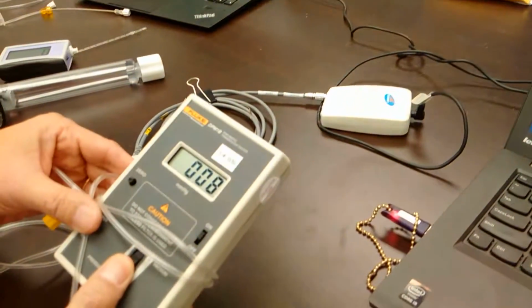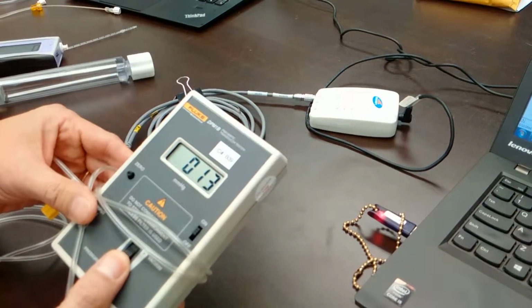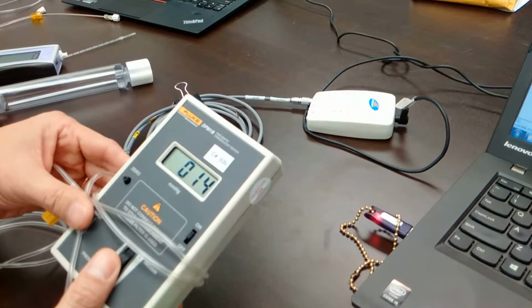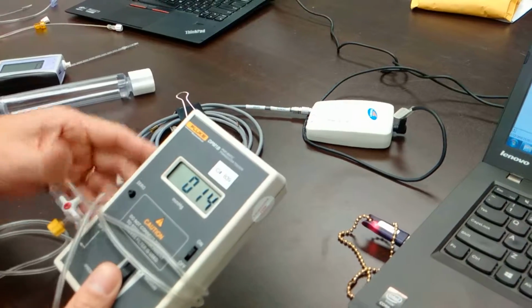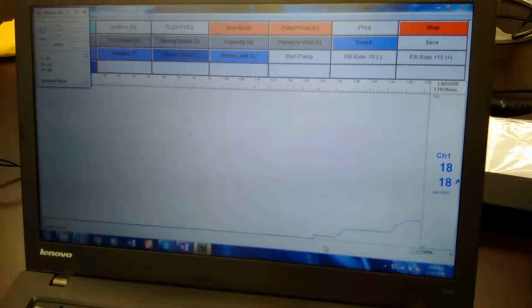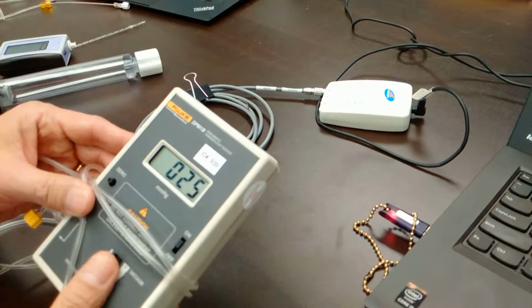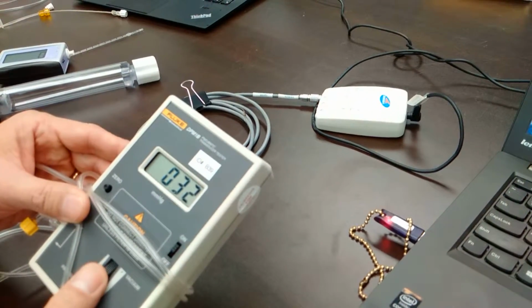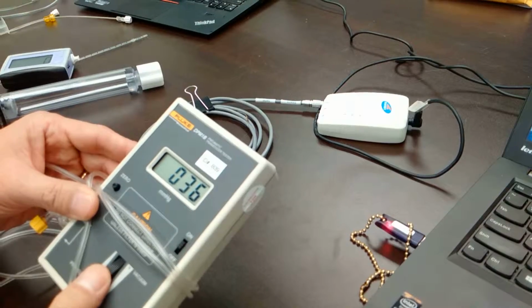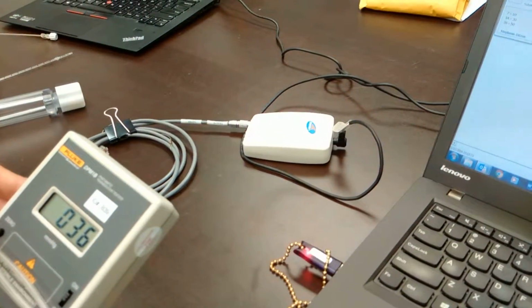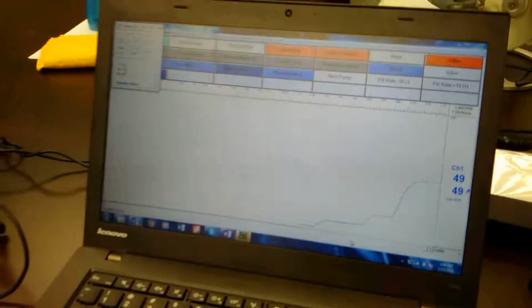If we go to 14, you'll see you get about 18. It's supposed to be 20. It's pretty close. Not quite bang on, but it's still not bad. And you dial it up to 36, and you're supposed to get 50. You pretty much get 50. So this is how a system actually gets calibrated.